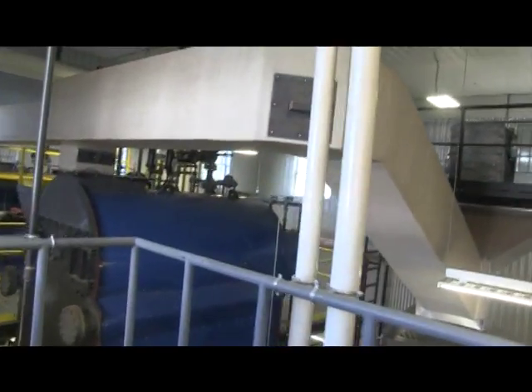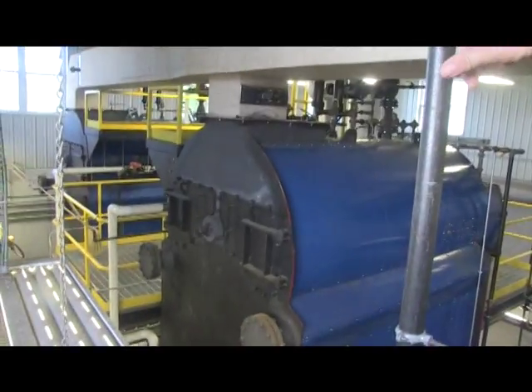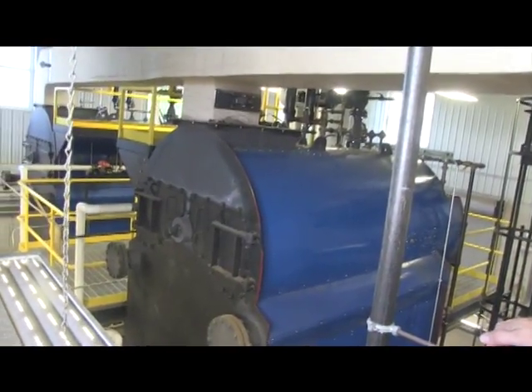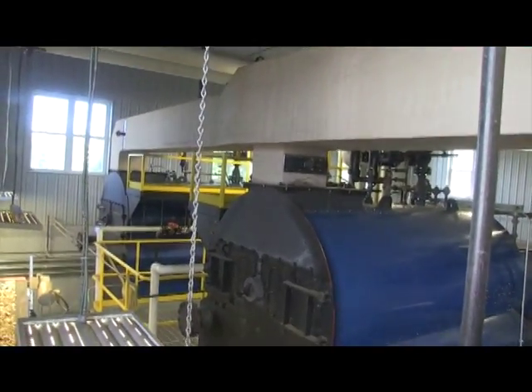So what we have here is two wood-fired steam boilers. The smaller one is the closest one to us. It's 150 horsepower. The further one away is a 200 horsepower steam boiler. We operate the boilers at 80 pounds steam pressure.